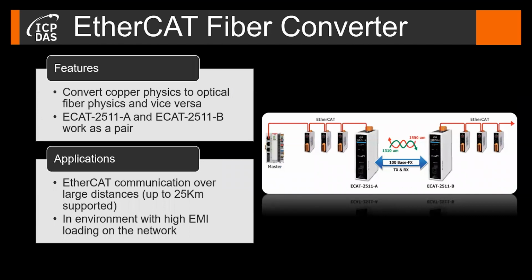The ICP-DAS EtherCAT fiber converter basically converts a copper signal into a fiber optical signal. The main application is to bridge larger distances between the slaves. Up to 25 kilometers is possible between slaves. In addition, it reduces the influence of electromagnetic interferences in an EtherCAT network to ensure stable operation in industrial environments with harsh electromagnetic disturbances.